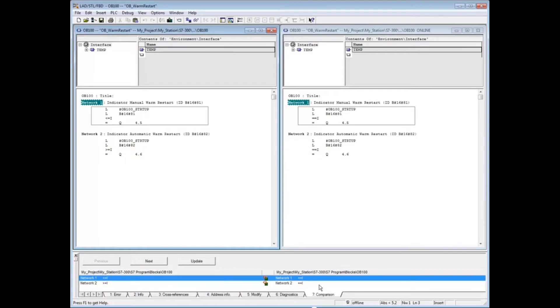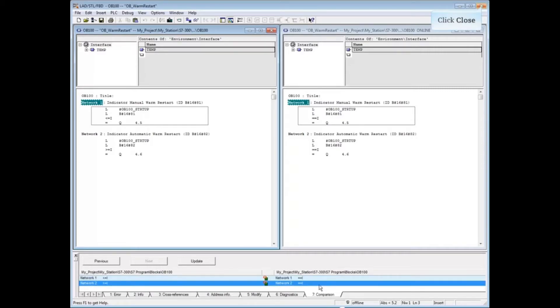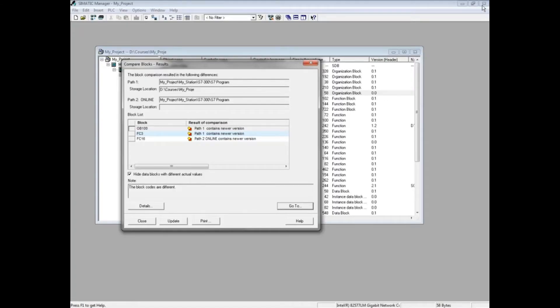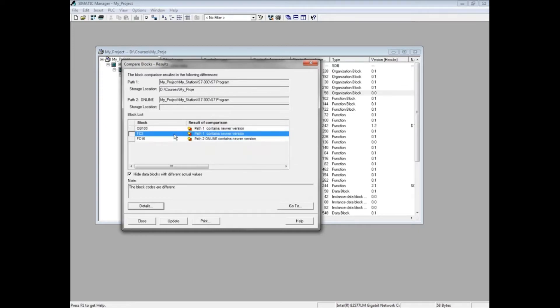We would now decide which block is correct and sync the two with a download if the offline block is correct, or close the offline block and perform a save to transfer the online block to the blocks folder. Close the programming editor.